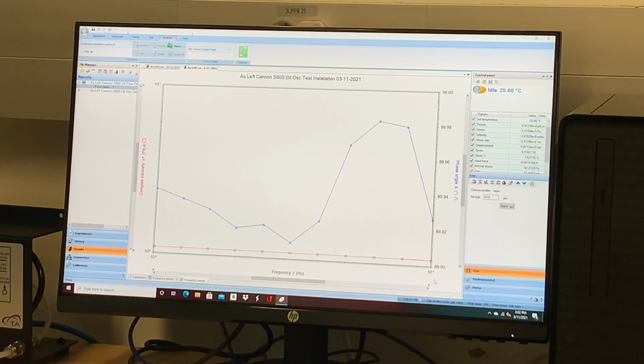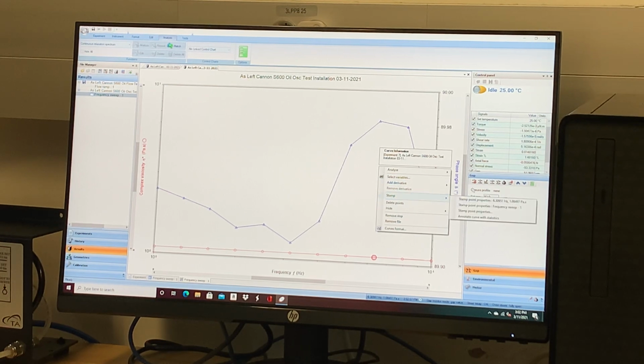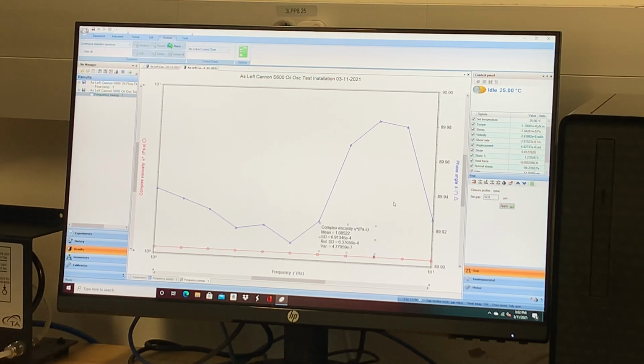Okay, so it went to idle. So now if we right click on a data point, I'm just going to annotate the curve with statistics, and the mean is 1.085. So typically I find the complex viscosities are usually a little higher, but it's always within the 3%, right? So you do an oscillation if you wanted to do some oil or fluid at a really high shear rate, because I've had people ask me, well, if you do that, oil's going to be all over the wall, you know? So just do a frequency sweep at high frequency. Okay?